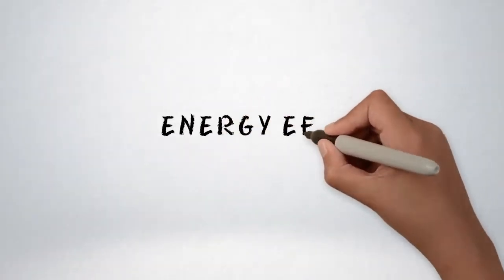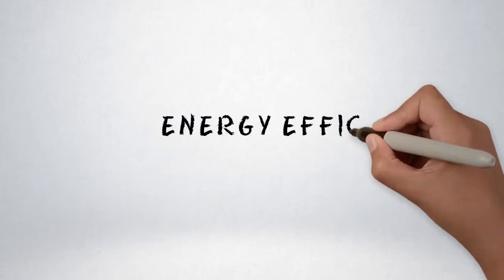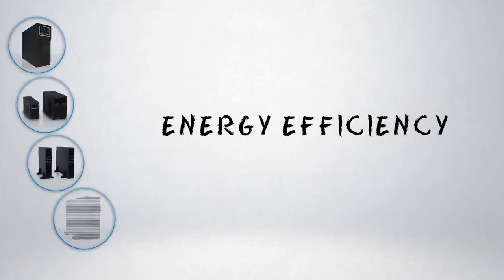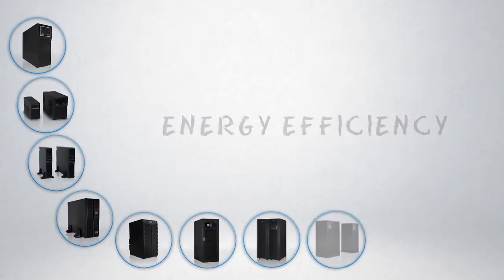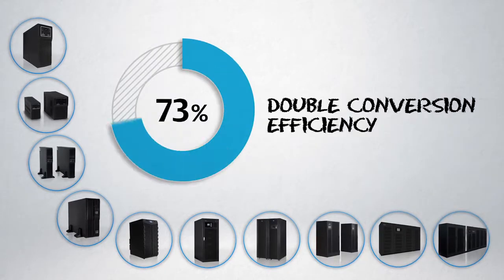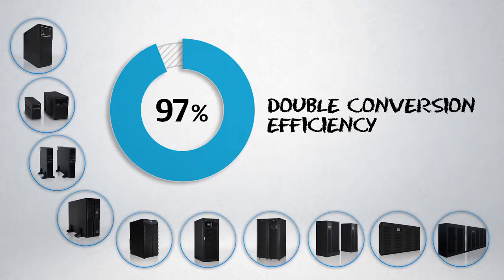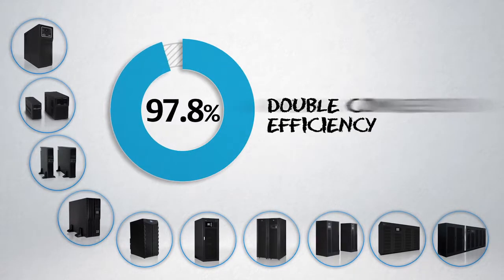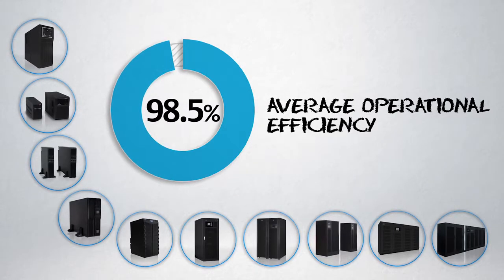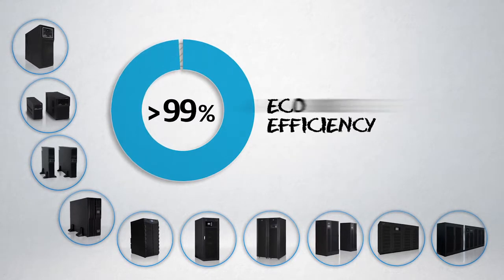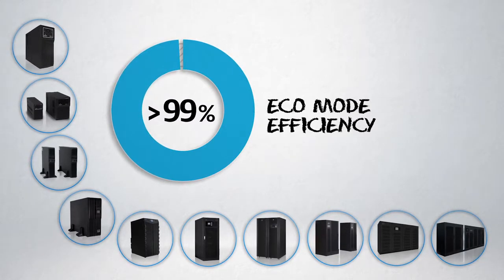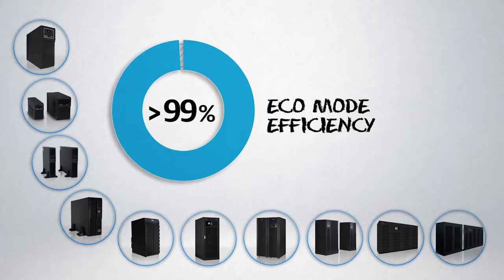Energy efficiency is one of our top priorities to help you reduce TCO. You can count on UPS with double conversion efficiency up to 97% at half load, average operational efficiency of 98.5% with eco-mode efficiency above 99% and intelligent paralleling feature that optimizes efficiency at partial load.